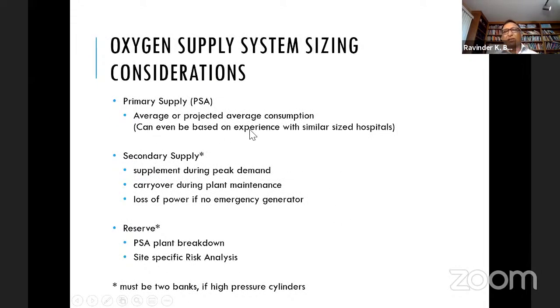So, on the primary supply, a lot of questions have been asked about how a hospital should size the plant. In my opinion, and by standard, the PSA plant should provide the average consumption of the hospital. Hospitals do surgeries in the morning and different things in the afternoon, so demand is not constant, it changes, with sometimes peak demand. Sizing a PSA plant for peak demand gives you a plant size much larger than needed, more complicated, more difficult to maintain, and unnecessary, it would just sit there.